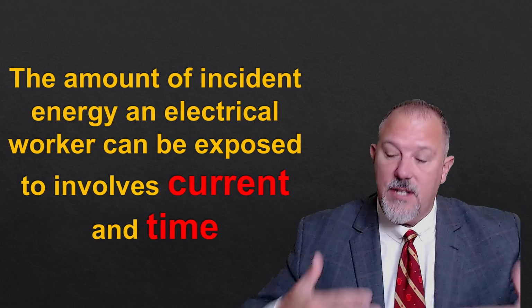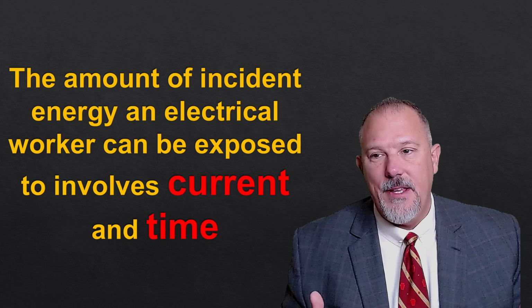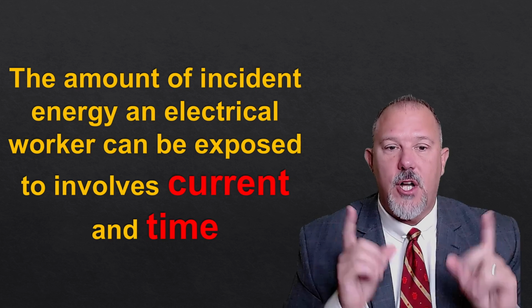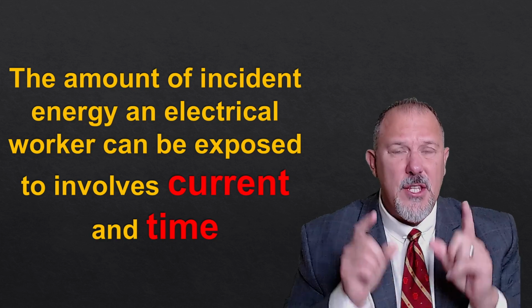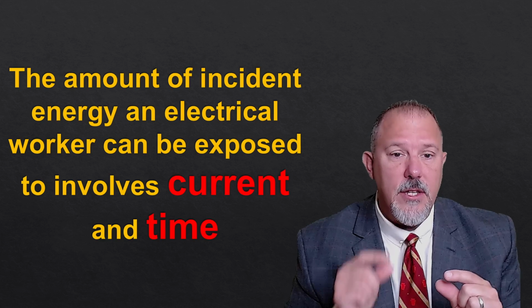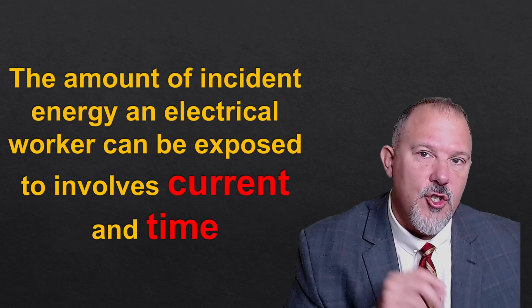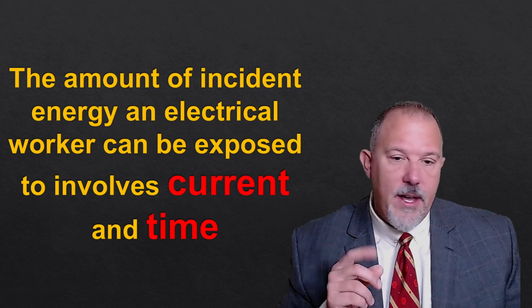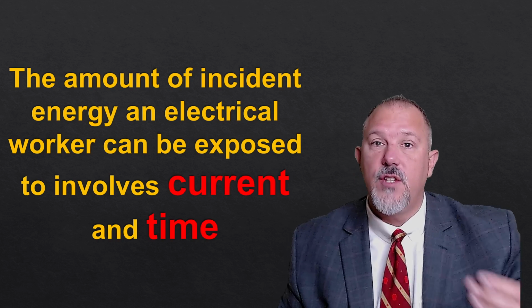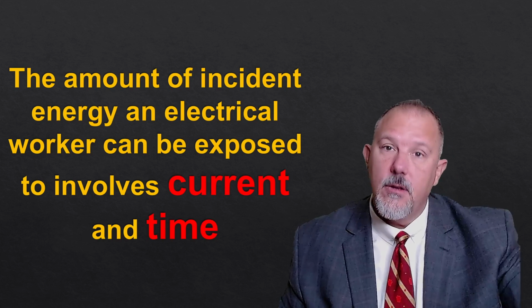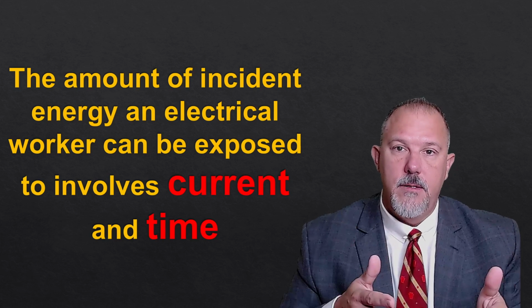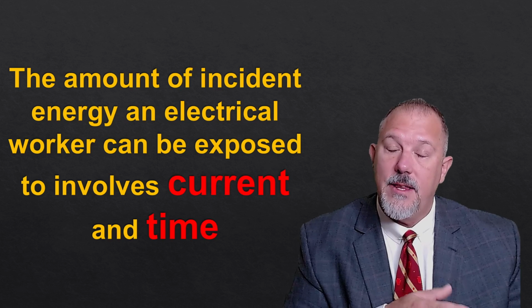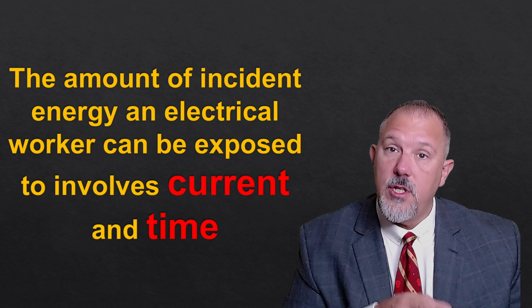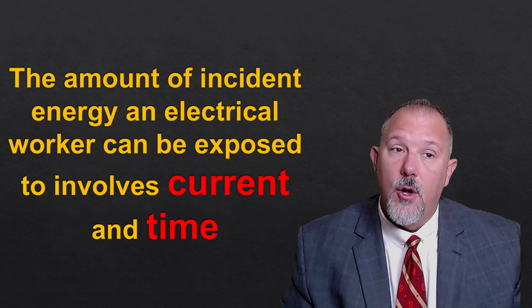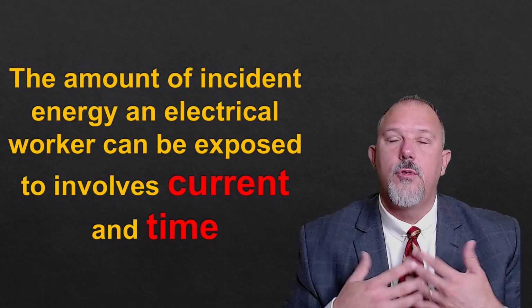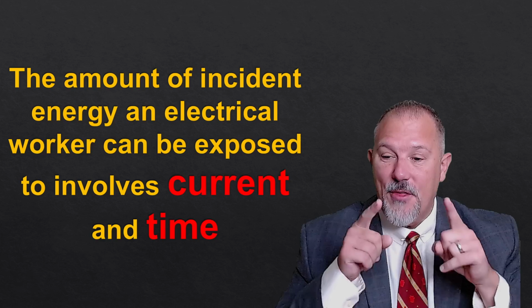And I've got to update this because we've just updated the IEEE 1584, and we know that the amount of incident energy is also dependent upon a few other parameters, which we'll talk about. But the two principal parameters that I want you to think about are current and time. And think about what you have control over and what you don't have control over. Do you have control over the current? And you may say, I sure do. I can add a transformer in and reduce the current. You sure can. I can add conductor length and reduce the current. But does reducing current always result in decreasing energy? And the answer to that question is no. Sometimes reducing current, I would almost argue, quite often, reducing current will produce more incident energy. And we're going to talk more about that in this hour as well.